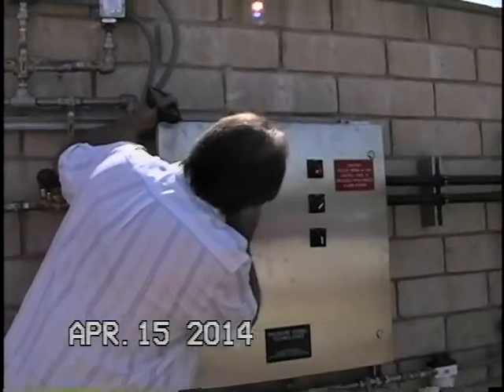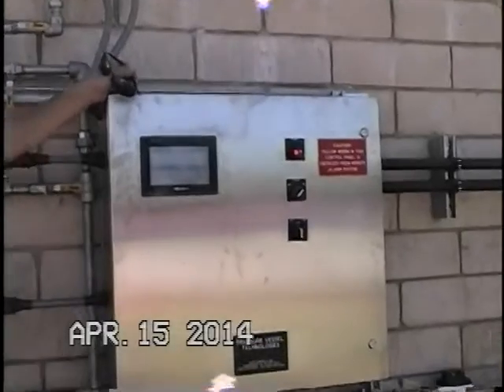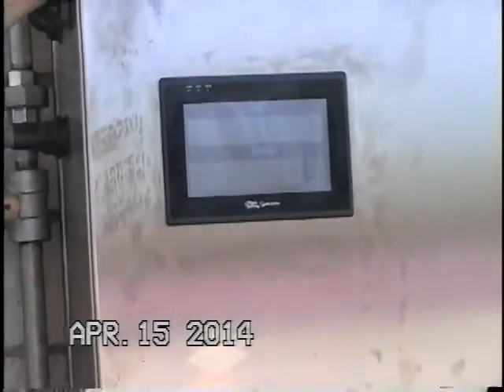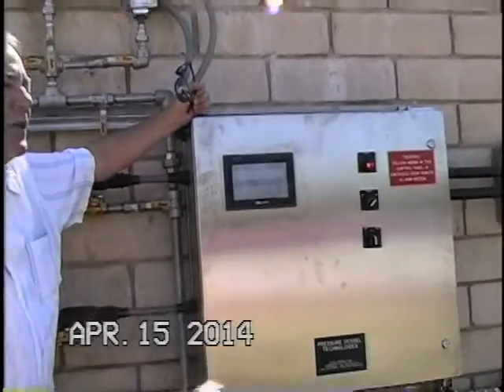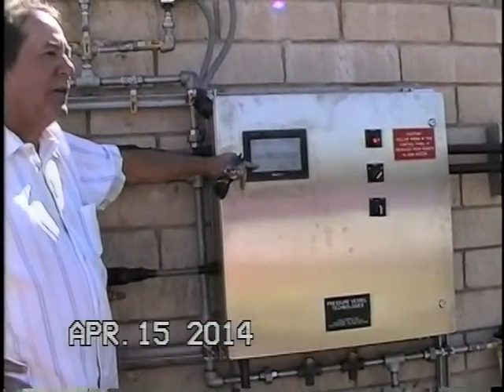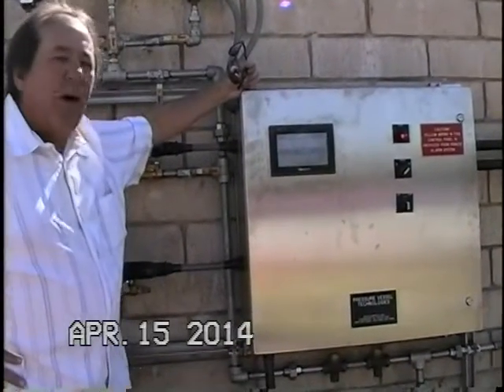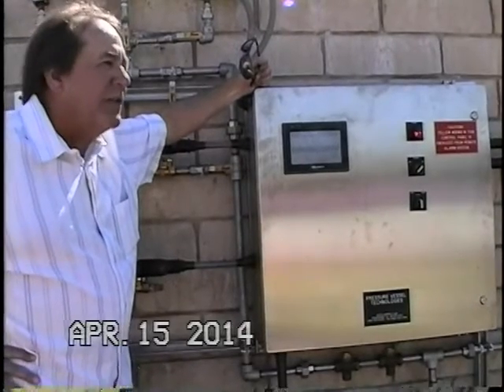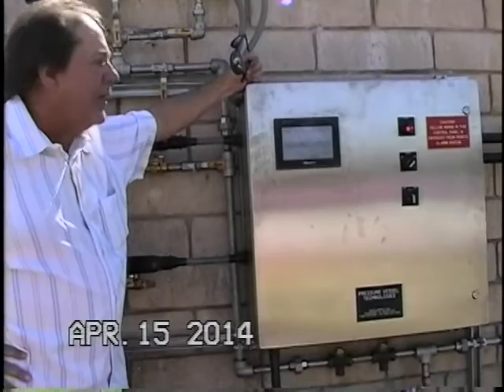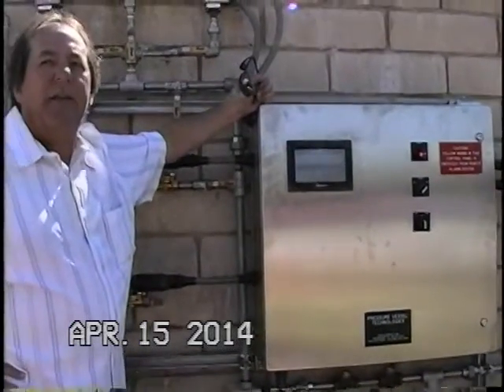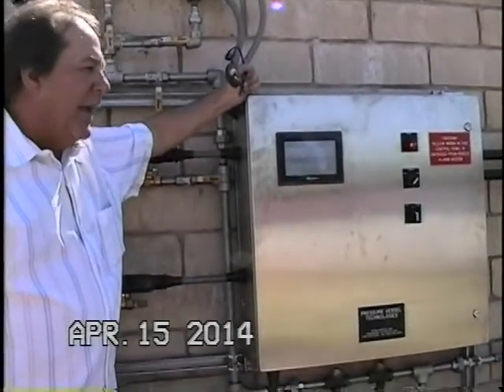The other nice feature on here is the alarm display. That screen gives you a log of events. The log gives you a time and a date of when these events occurred. The only time it goes into the log is if you've come out here and acknowledged that you've had an event, whether it be a high alarm or low alarm event. You must acknowledge it, and then it will transfer over into the log. That alarm will stay maintained until it's acknowledged. So an operator must come out here, hit the reset button, and the alarm will go away. So it must be acknowledged.